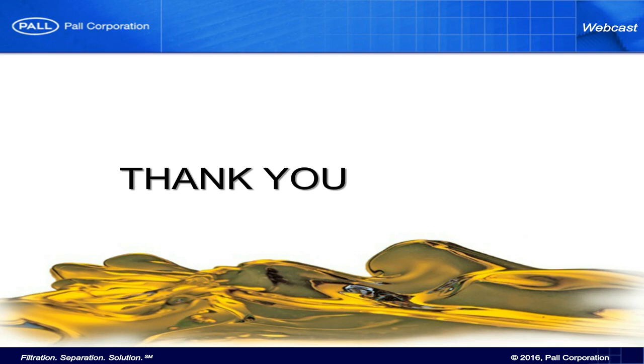So a question by John: what oil purification system does Pall offer for large power generation turbine oil reservoir? It basically is a question of size, right? So the bigger reservoir you have, the bigger the purifier will be. And when I say big purifier, it's simply a question of flow rate. So there is a practical method to calculate how big your flow rate should be. And it's a function of how many times you need to recirculate a certain amount of oil through a purifier.